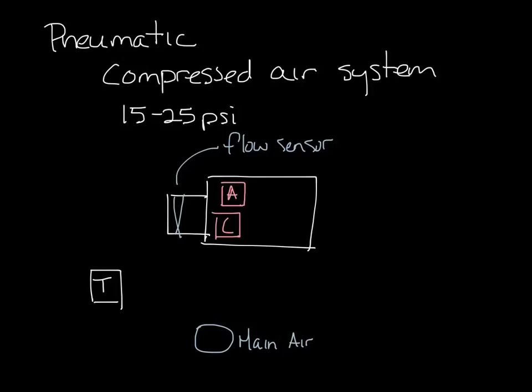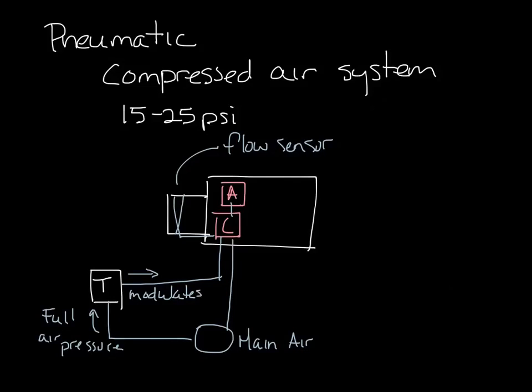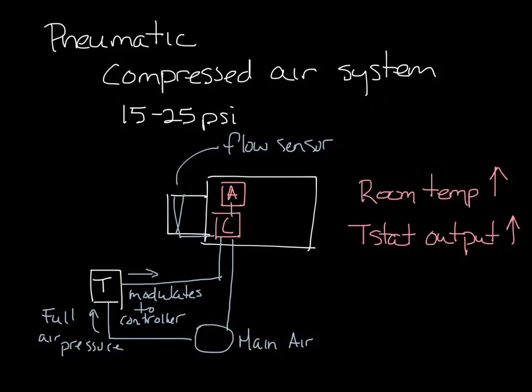So the main air system is connected to the thermostat and the controller. The controller is also connected to the flow sensor and the thermostat, and it's connected to the actuator. The thermostat receives full air pressure from the main supply air. And it modulates the output pressure that goes to the controller to tell the controller whether it needs to open or close the damper. So when the room sensor senses an increase in temperature, the thermostat output pressure increases as well to the controller, which tells the controller to open the damper and supply more air to the space.